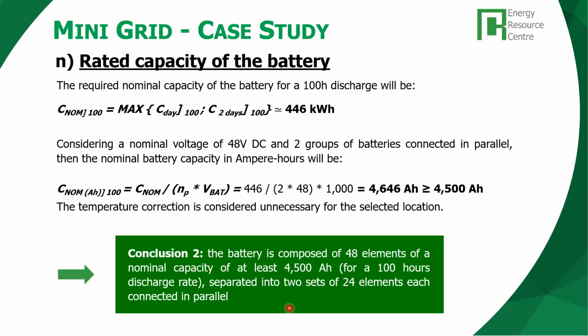So conclusion number 2. The conclusion number 2 is that for our mini grid, 137 connections, worst case analysis in the month of January, with the consideration of a genset in the island of Chifi in Zambia, we will be needing a rated battery capacity over 100 hours of discharge of 446 kilowatt hour. If we consider a battery bank of battery cells of 2 volts each, we want to put a battery bank of 48 volts nominal in DC.